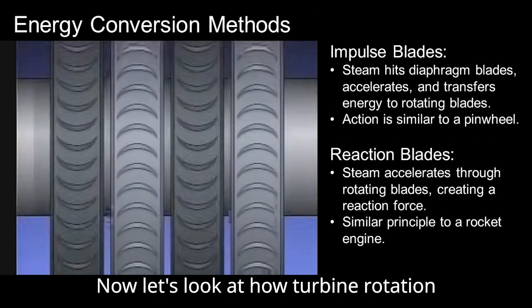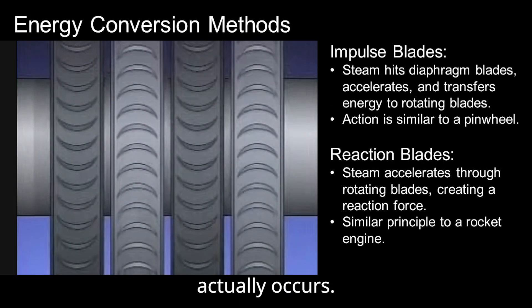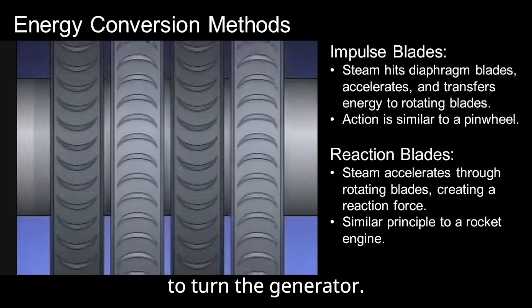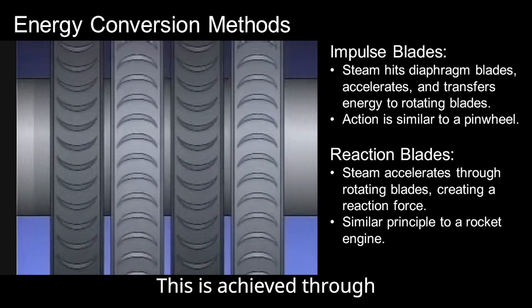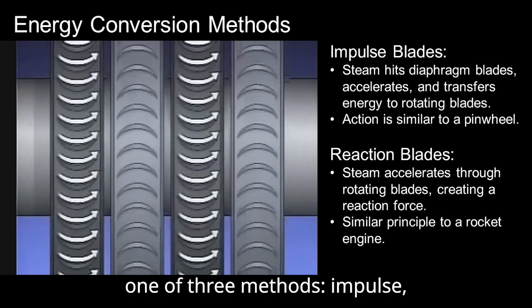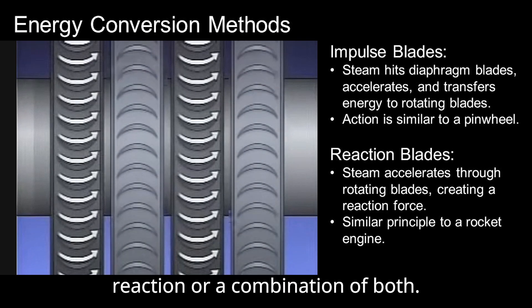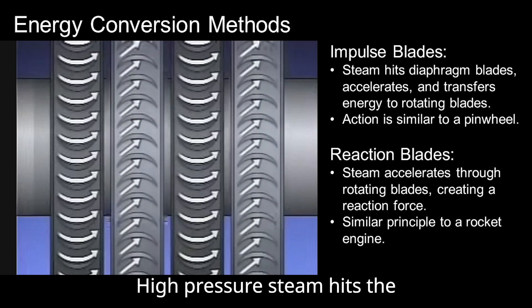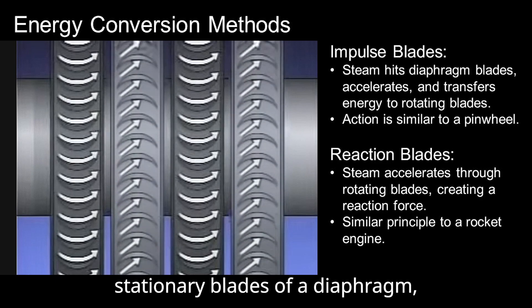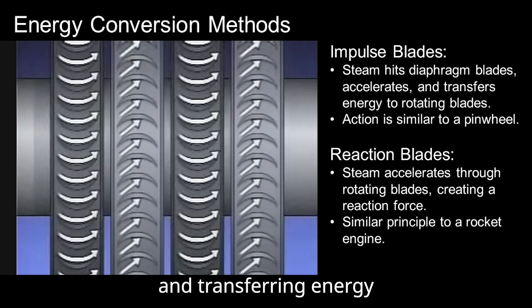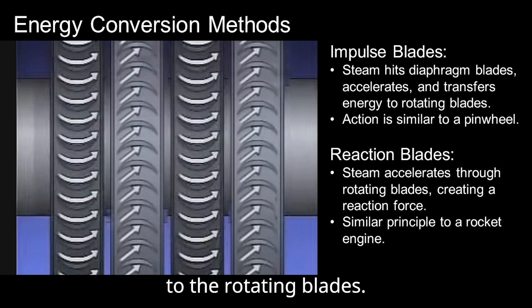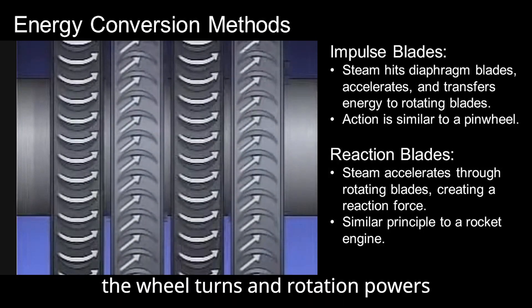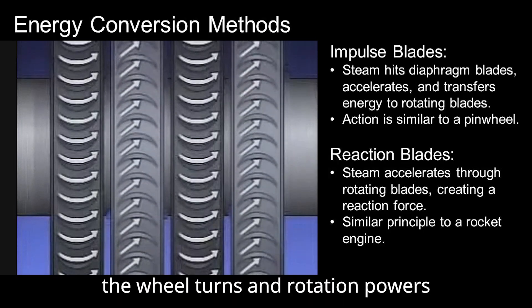Now let's look at how turbine rotation actually occurs. The turbine's job is to convert steam energy into mechanical energy to turn the generator. This is achieved through one of three methods: impulse, reaction, or a combination of both. High pressure steam hits the stationary blades of a diaphragm, speeding up the flow and transferring energy to the rotating blades. As the steam strikes the blade, the wheel turns and the rotation powers the turbine shaft.